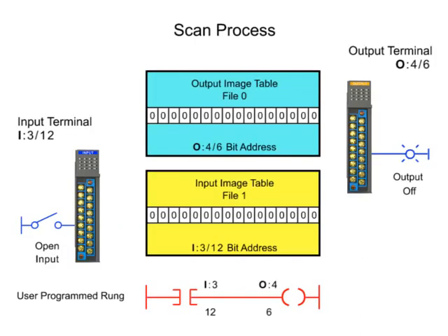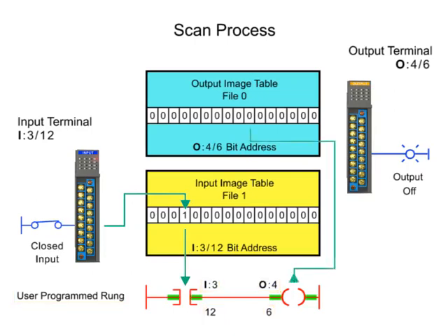The entire scan process is demonstrated further here. When the limit switch is activated, the input module detects a voltage and an on condition is updated in the input table with a value of 1. During the execute program step, the PLC sets the input and output instructions on. The output status is updated with the light changing state from off to on as defined in the ladder logic.